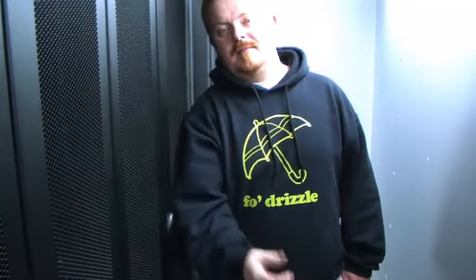Again, just a few points to note. Each fan is isolated. So if I turn that off, that fan will switch off. The rest of them will go into a fail-safe mode in this aisle. Here's the noise.